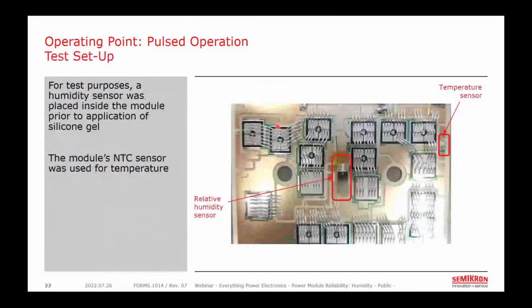So how do we measure that? Well, inside this test module we have both a relative humidity sensor and a temperature sensor. Both of these are mounted onto the substrate of this power semiconductor module underneath the silicone gel. This temperature sensor is standard equipment that's soldered inside a production Semikron module along with the chips. And this humidity sensor has just been placed here manually for this test. This is not a standard accessory.